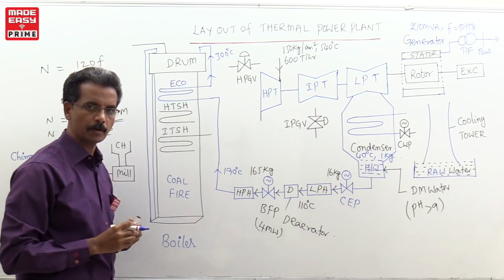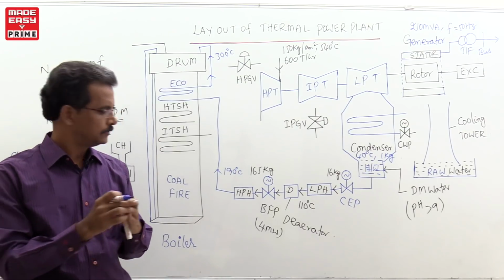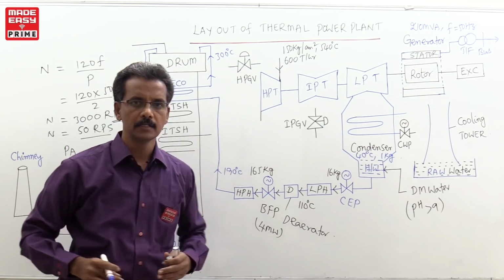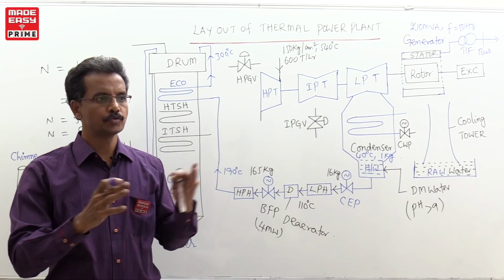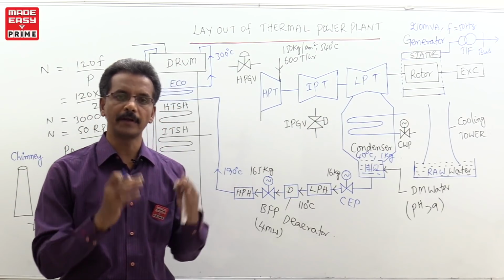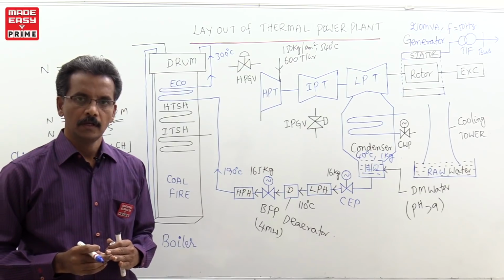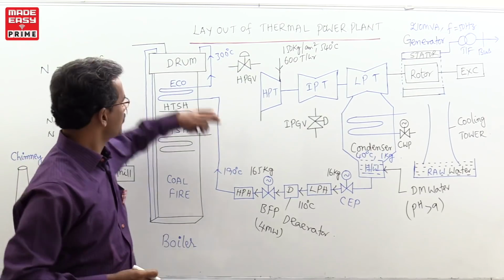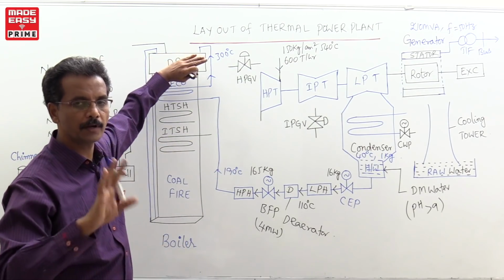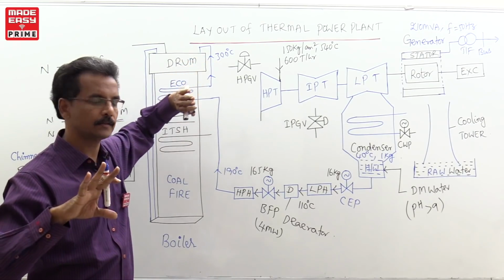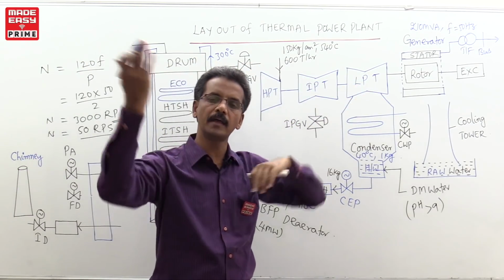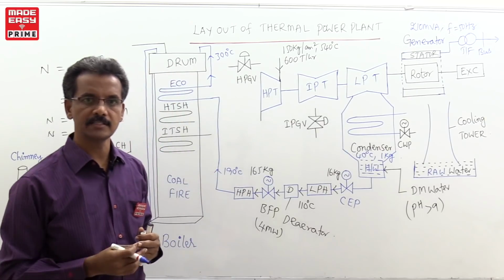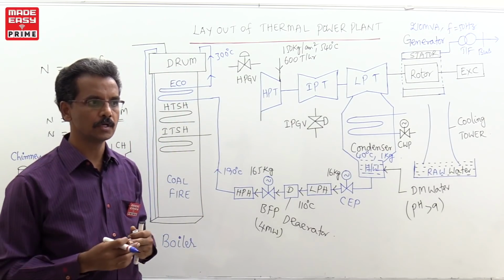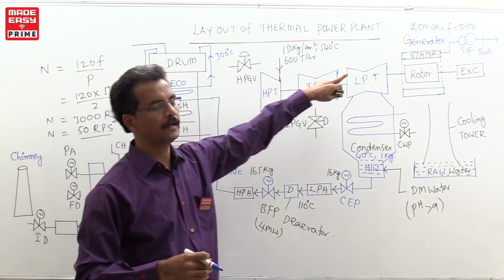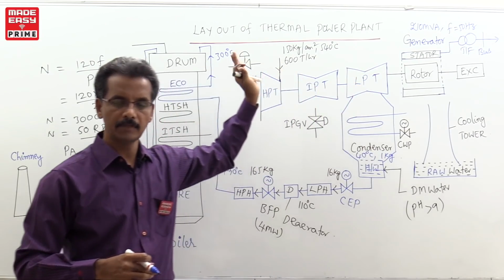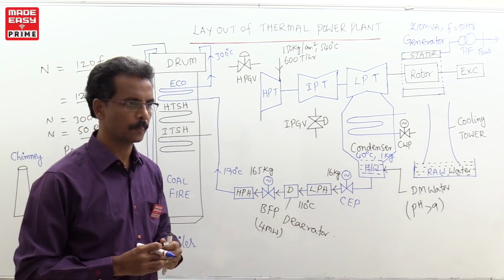Now, I want to point out one important thing. Basically, in thermal plants, one type is the supercritical thermal plant and the other is the subcritical thermal plant. Supercritical thermal plants do not have this drum. Normally, supercritical thermal plants have generators of more than 500 MVA capacity. There, supercritical thermal plants are used, right.